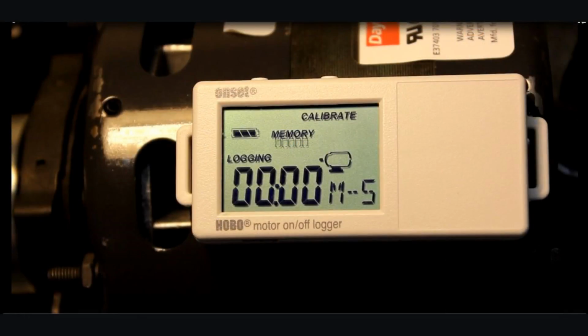We have our UX90-004 Motor On Off Logger connected to a little motor using the four rare earth magnets. It's being held by those magnets that are included in the case. You can see here that it is logging, but it's not incrementing any runtime because the motor's not running. There's a couple of icons I want to call your attention to. You can see the large digits, that's runtime in minutes and seconds. To the right of that, there's something that says MS, that's minutes and seconds. If it was running for longer periods of time, that would switch to H and M, so hours and minutes. And it can actually go up to days and hours as well.